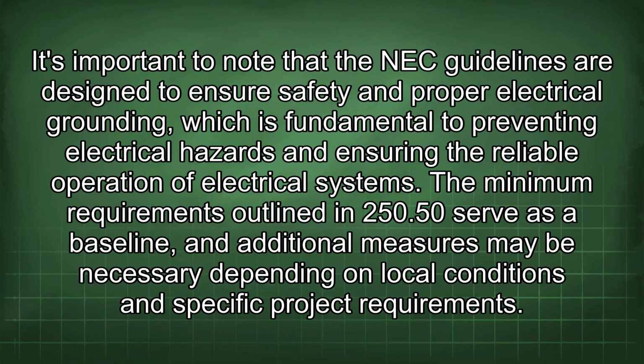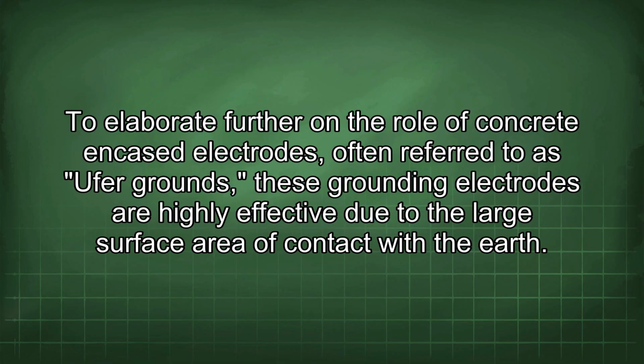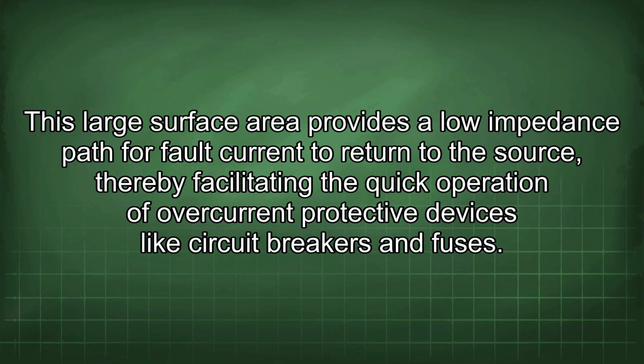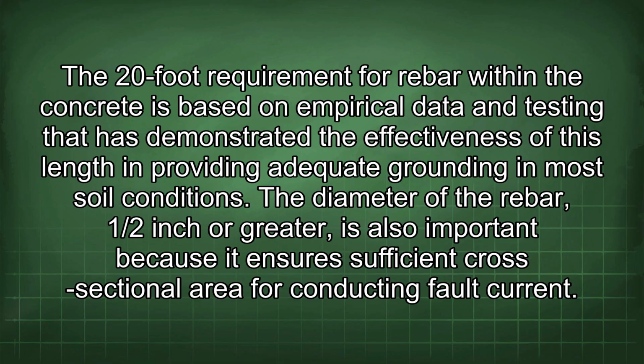and specific project requirements. To elaborate further on the role of concrete encased electrodes, often referred to as UFER grounds, these grounding electrodes are highly effective due to the large surface area of contact with the earth. This large surface area provides a low impedance path for fault current to return to the source, thereby facilitating the quick operation of overcurrent protective devices like circuit breakers and fuses. The 20-foot requirement for rebar within the concrete is based on empirical data and testing that has demonstrated the effectiveness of this length in providing adequate grounding in most soil conditions.